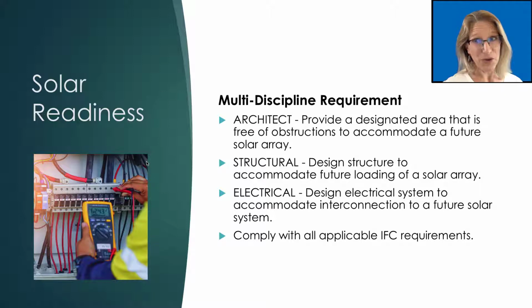What is unique about this new energy code requirement is that it requires a fair amount of collaboration between multiple disciplines to cover all the necessary elements. So for the architect, they are required to provide a designated area that's free of obstructions that will accommodate a future solar array. The structural engineer needs to design the structure of the roof to accommodate future loading of the solar array. The electrical engineer or contractor needs to design an electrical system that accommodates the interconnection that is necessary for a future solar system. And this section also highlights that all applicable IFC requirements also apply, which is a given.